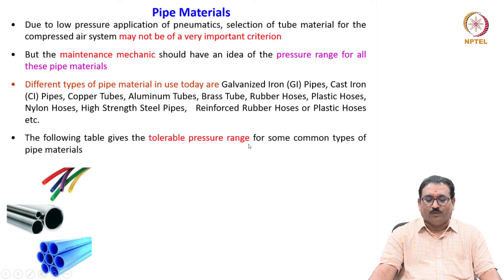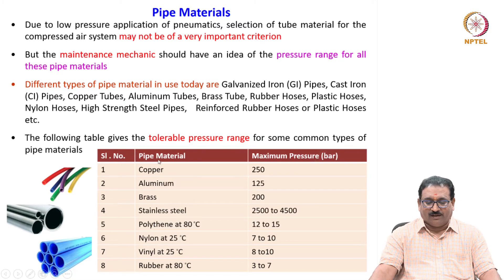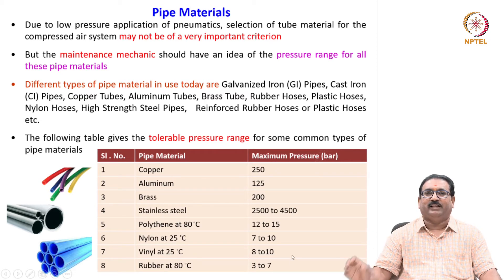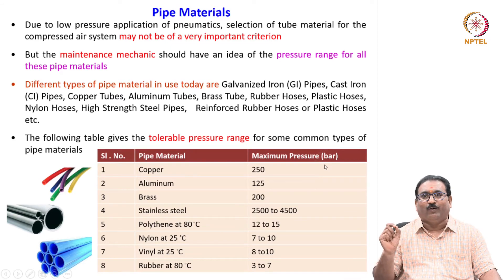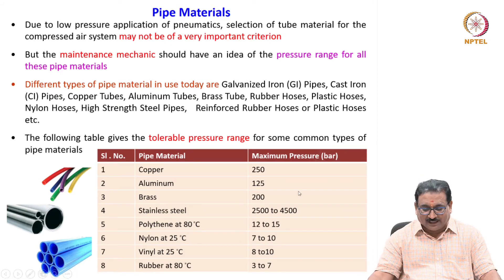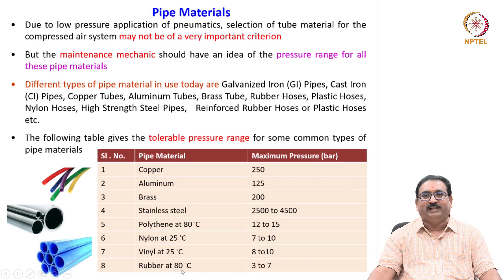The following table gives the tolerable pressure range for common pipe materials. Copper pipe can withstand up to 250 bar; aluminum, 125 bar; brass, 200 bar; stainless steel, 2500 to 4500 bar. Nylon can handle 7 to 10 bar; vinyl, 8 to 10 bar; rubber at 80°C, 3 to 7 bar. The key point is that each pipe and tubing material has a maximum pressure range it can withstand.